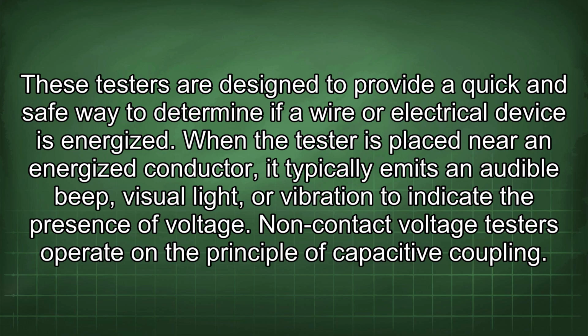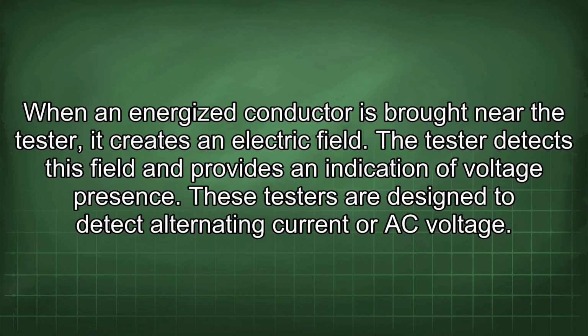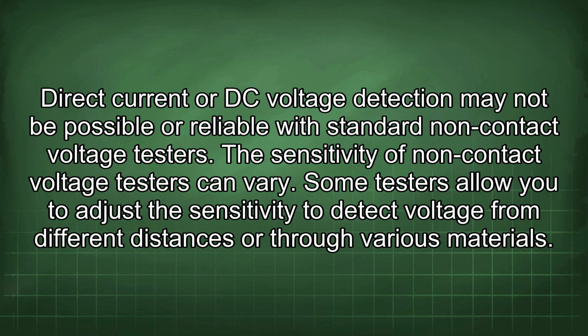Non-contact voltage testers operate on the principle of capacitive coupling. When an energized conductor is brought near the tester, it creates an electric field. The tester detects this field and provides an indication of voltage presence. These testers are designed to detect alternating current or AC voltage. Direct current or DC voltage detection may not be possible or reliable with standard non-contact voltage testers.